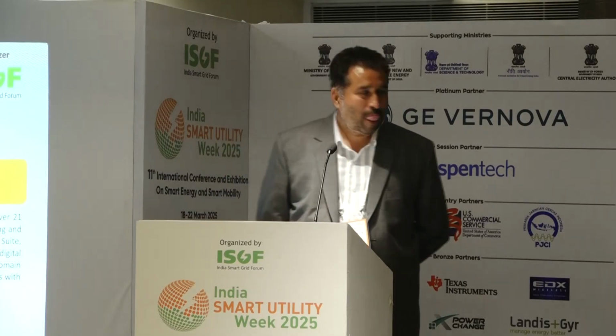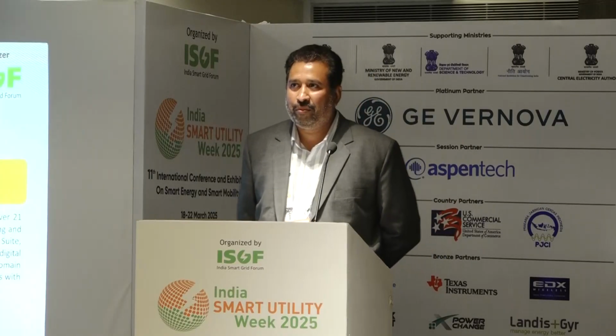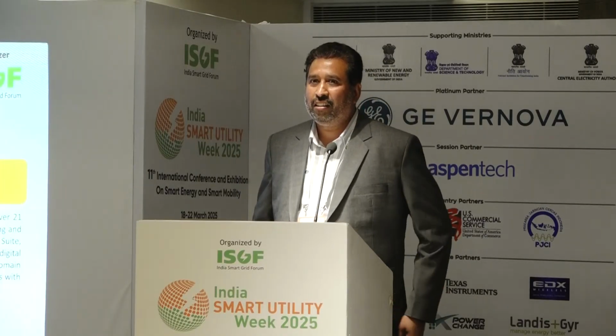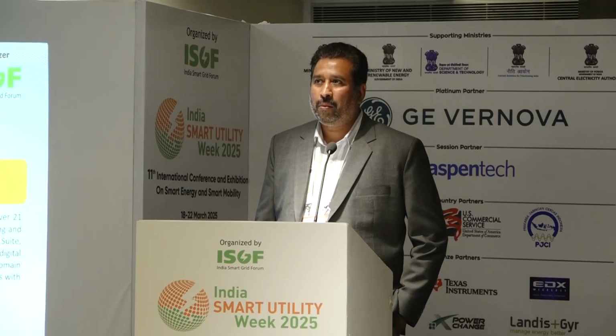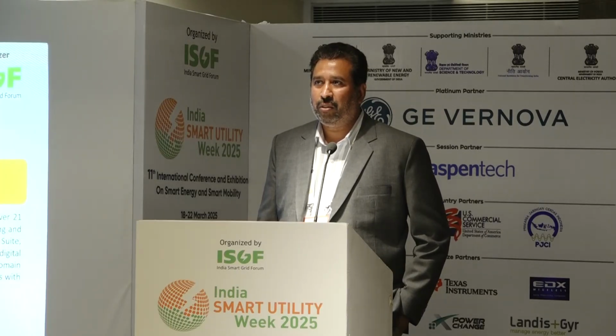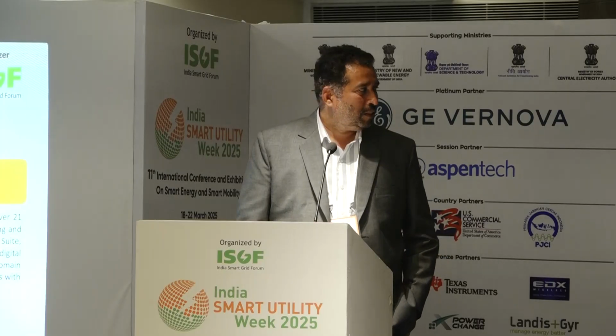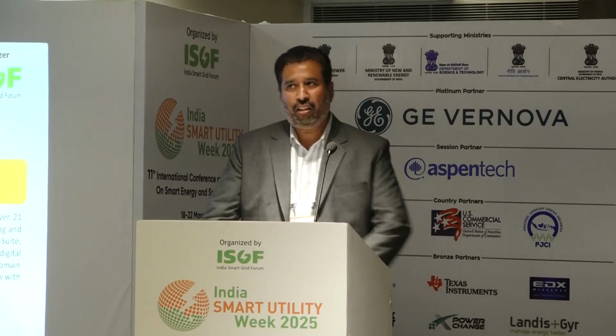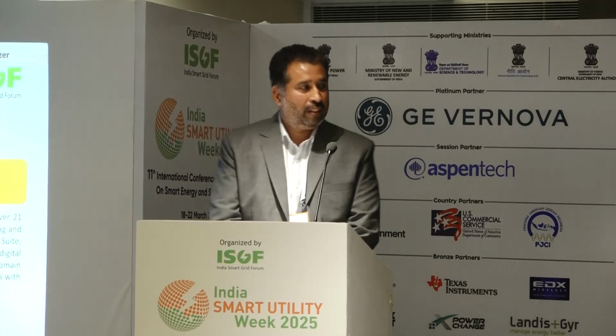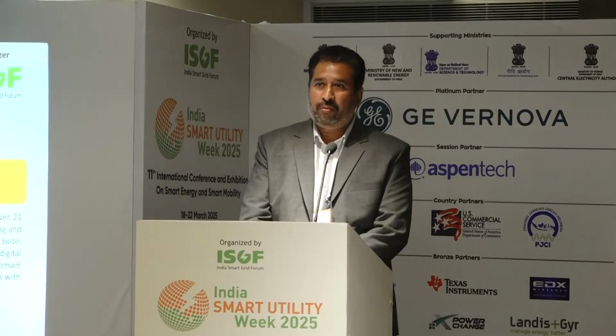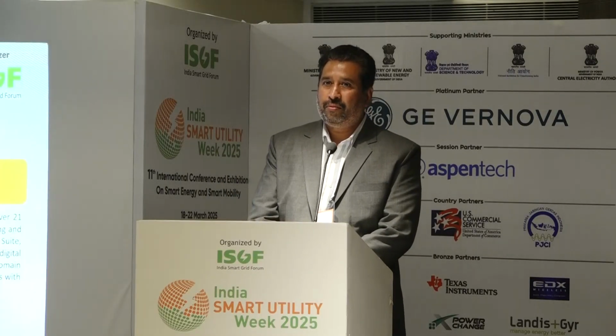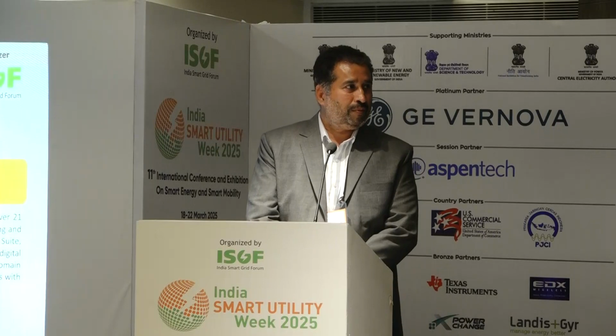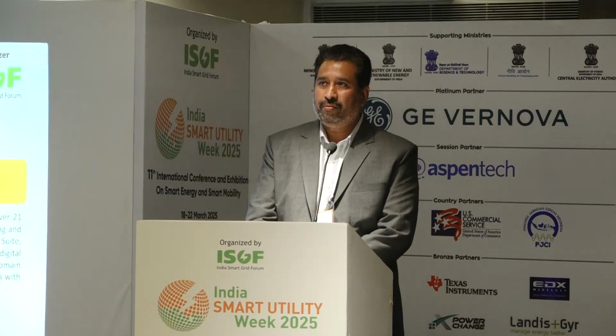Their SCADA is up to 11 kV. If a fault happens on a particular pole of a feeder, there is no way to detect it automatically, so that has to be manual. That's the limitation of SCADA at the substation level, 11 kV level, which is the DMS level. Even after DMS, you're monitoring up to the breaker, but if the fault is in that part of the network, you may not be able to detect it either, so then it requires manual intervention.